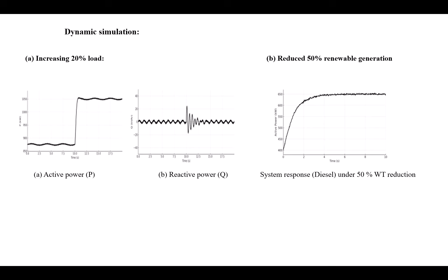For scenario 2, the wind power suddenly drops by 50%, and the system responds as diesel output increases immediately to replace the lost wind source. Batteries provide temporary support, and the system returns smoothly to steady state. This shows the control system is capable of handling renewable variability.